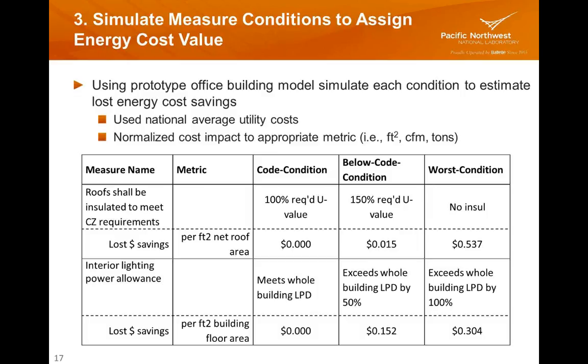So showing here, for example, for the roof: if it has 100% of the required U value, the code condition, there's no lost energy cost savings. Simulation showed us that at 150% of the required U value, that was worth 1.5 cents per square foot of roof area. And if there was no insulation at all in the roof, 53.7 cents - the worst condition.